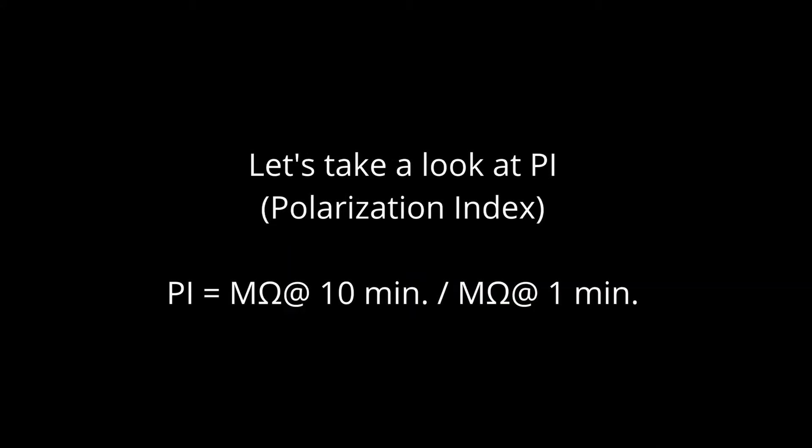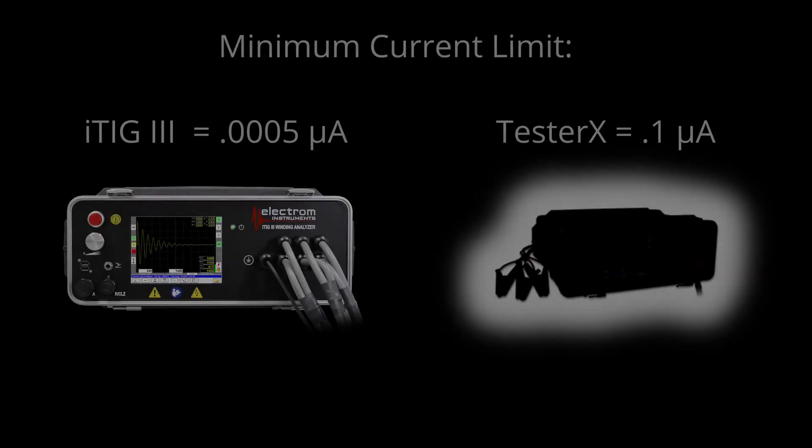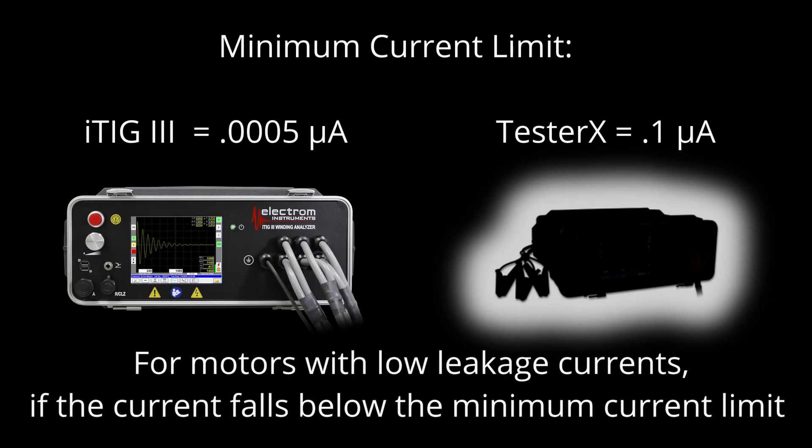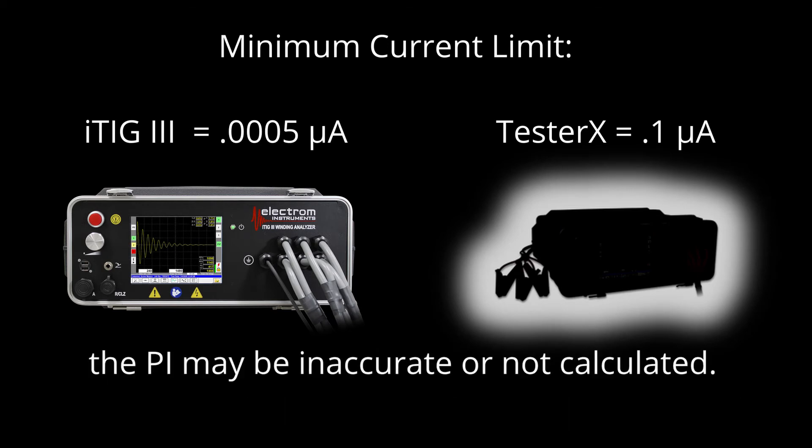Let's take a look at PI, or polarization index, where PI equals megaohms at 10 minutes divided by megaohms at 1 minute. For motors with low leakage currents, if the current falls below the minimum current limit, the PI may be inaccurate or not calculated.